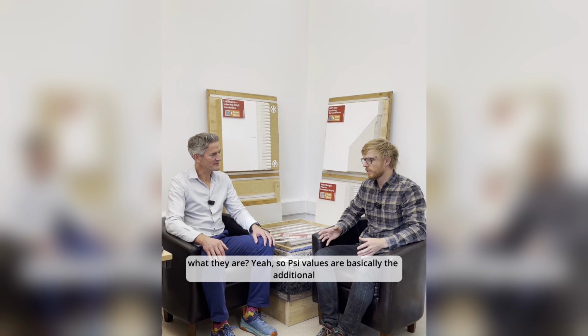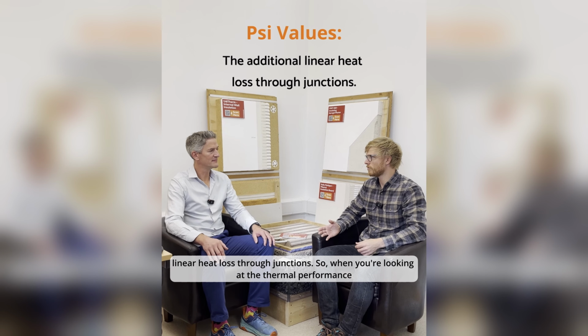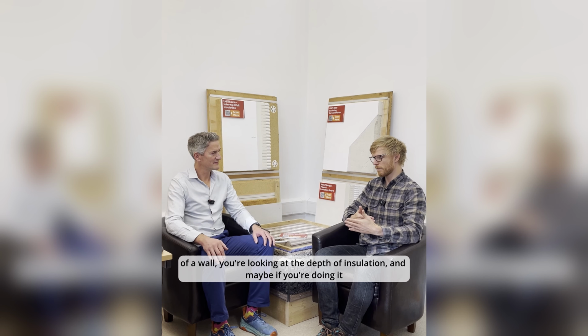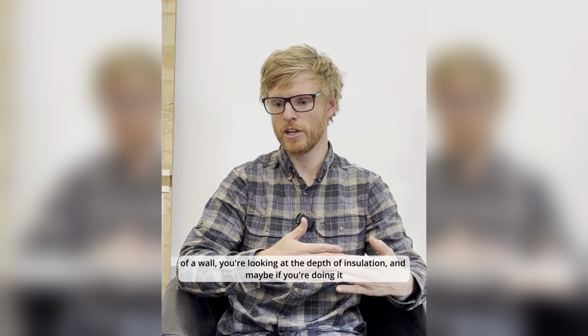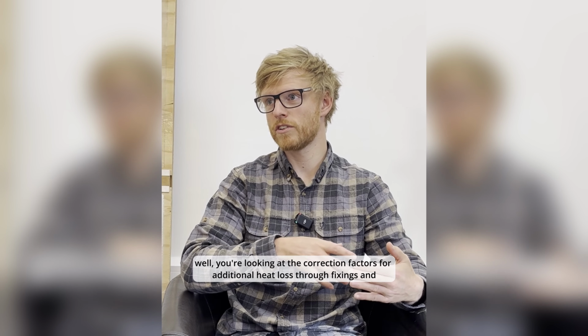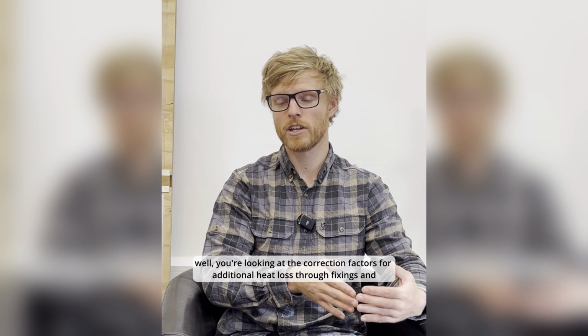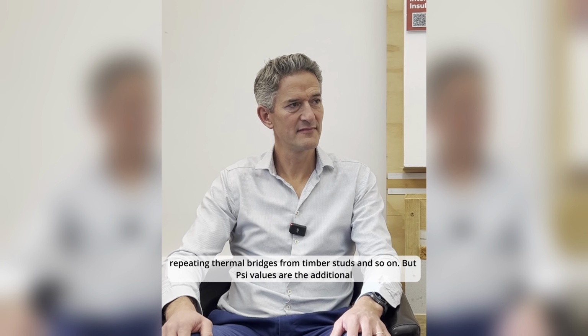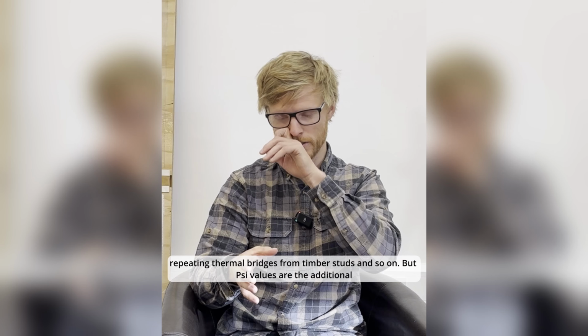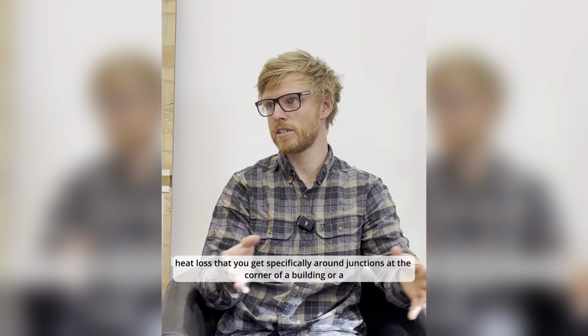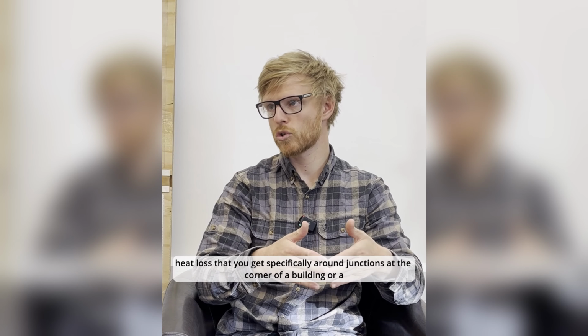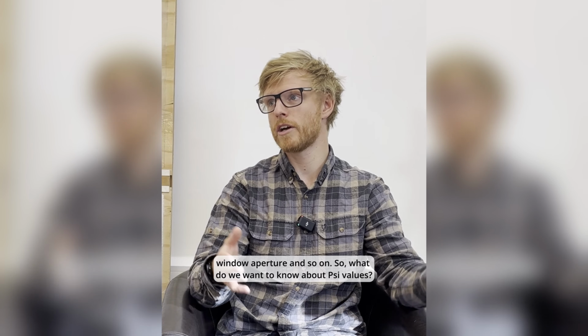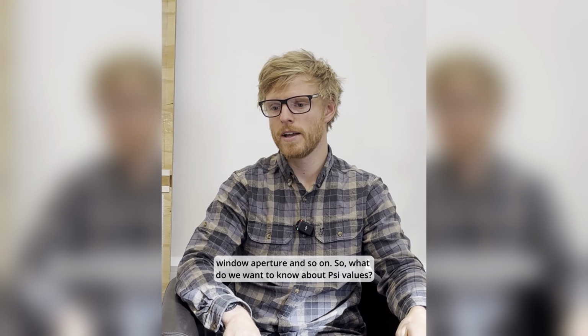Yeah, so psi values are basically the additional linear heat loss through junctions. When you're looking at the thermal performance of a wall, you're looking at the depth of insulation, and maybe if you're doing it well, the correction factors for additional heat loss through fixings and repeating thermal bridges from timber studs and so on. But psi values are the additional heat loss that you get specifically around junctions, at the corner of a building or a window aperture and so on.